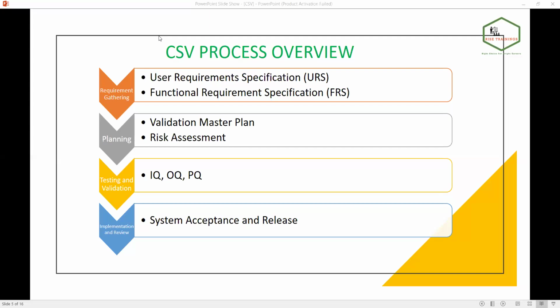Here, how do we ensure IQ and OQ? IQ ensures our design specification, whether the software is meeting our design or not. Operation qualification ensures the functionality of the software or instrument, or whatever it is. Performance qualification ensures our user requirements. You developed a user requirement specification initially, and in testing you ensure that all your requirements meet your criteria or not. That is the main document that closes the validation process. Performance qualification has to be performed by the end users who are going to use the software, in the validation environment.